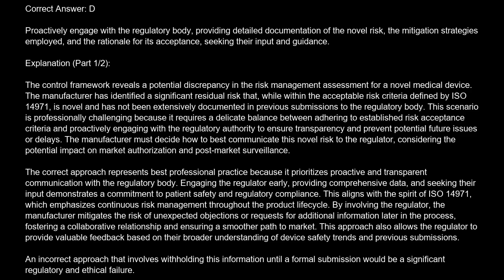The manufacturer has identified a significant residual risk that, while within the acceptable risk criteria defined by ISO 14971, is novel and has not been extensively documented in previous submissions to the regulatory body. This scenario is professionally challenging because it requires a delicate balance between adhering to established risk acceptance criteria and proactively engaging with the regulatory authority to ensure transparency and prevent potential future issues or delays.